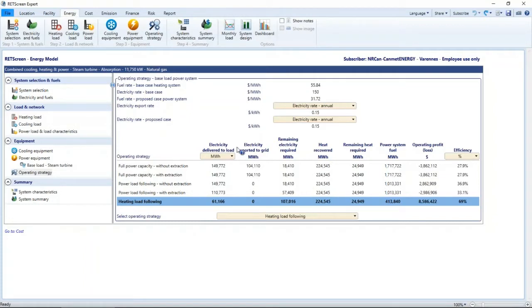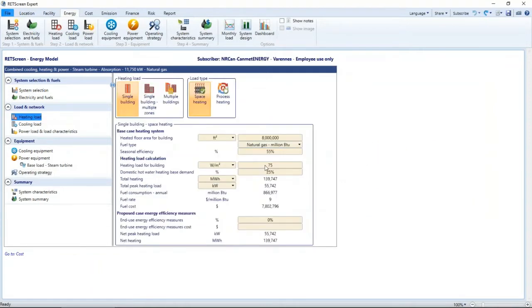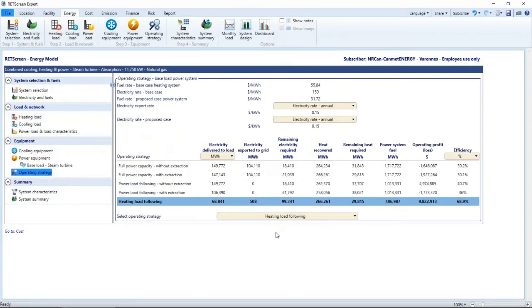If I go back to the heating load section and increase the heating load, I will then see that both the electricity delivered to the load and heat recovered vary depending on the operating strategy because of the extraction port option. I will now click on Undo to go back to the original heating load. The heating load following shows the best operating profit and the best overall efficiency.